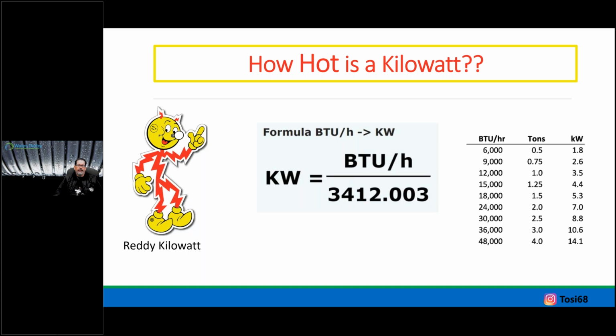So for 1 kilowatt, there's 3,412 BTUs. Let's say 1 ton of refrigerant, right? 12,000 BTUs, 1 ton, that's 3.5 kilowatt. So associating across different sources makes us more comfortable. That's why I did this.